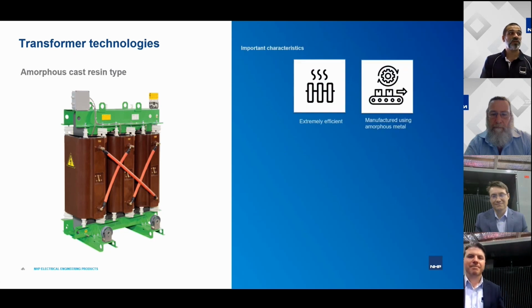Thanks, Nick. Yeah, so another thing with cast resin transformers, or transformers in general, amorphous core is something that's been talked about for many, many years. Essentially, a transformer has two main types of losses. You've got no-load losses, which are your core losses, and load losses, which are your coil or copper losses, as they're referred to.